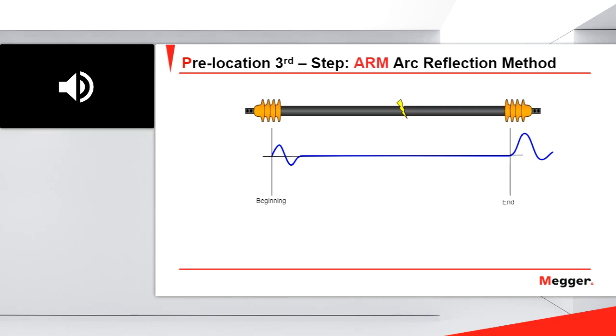Now we will see a short, because when the arc is active, what we have is a temporary short between the conductor and the concentric. When this arc is active, the high voltage pulse trace will look like this one. And at this point, where both traces, the blue one and the red one, the low voltage and the high voltage trace, separate, is where we have the fault. And we have prelocated the fault.